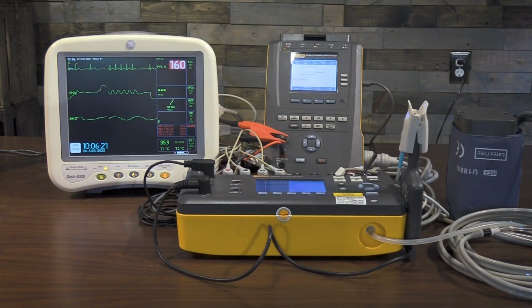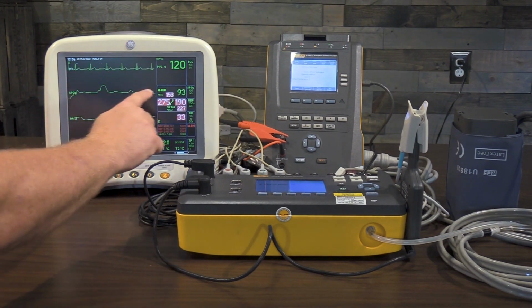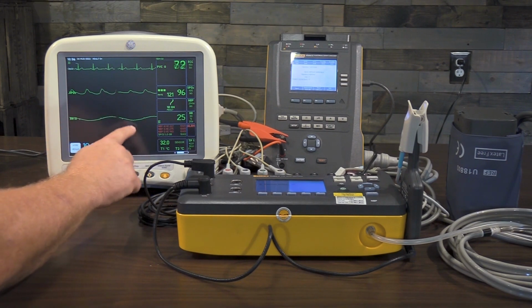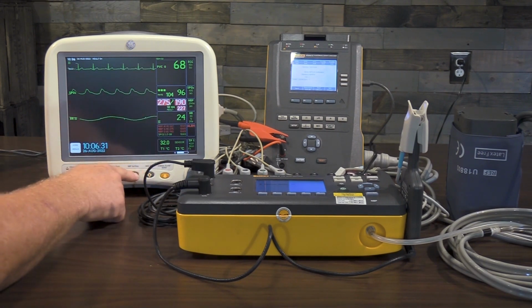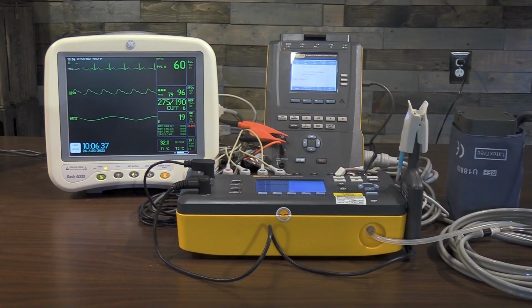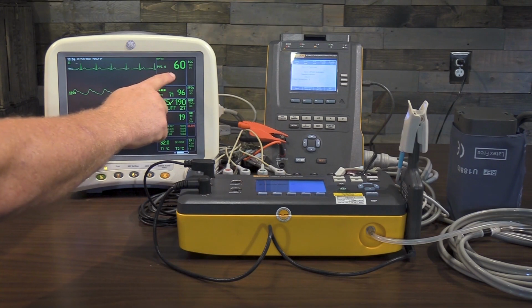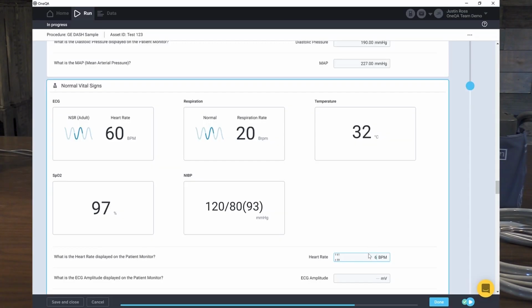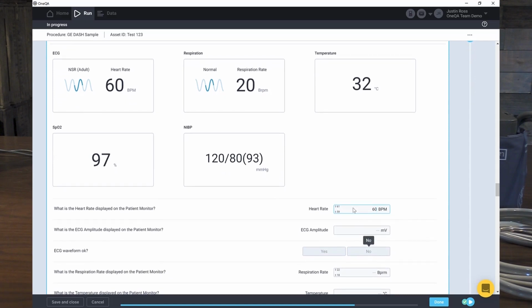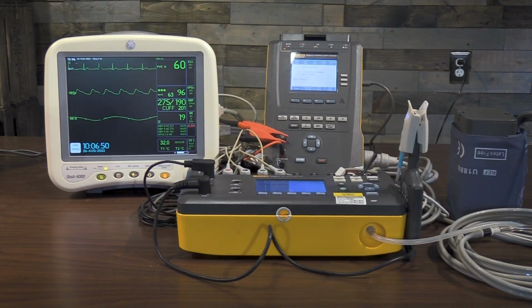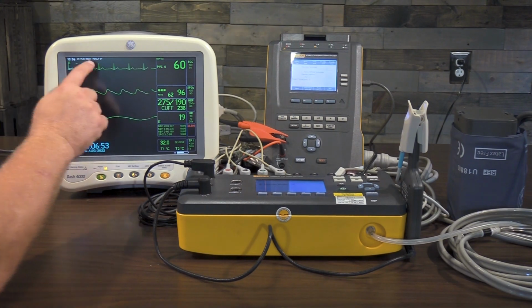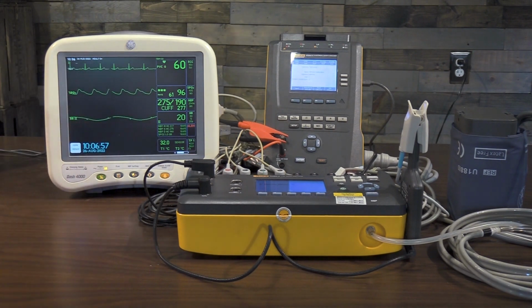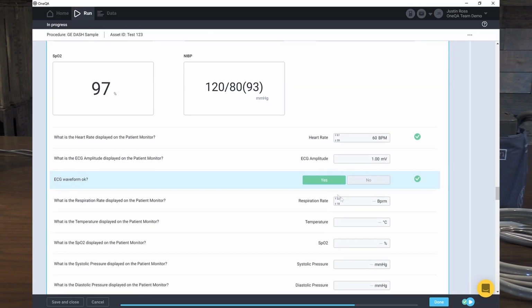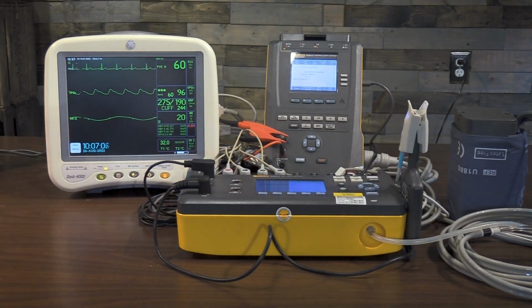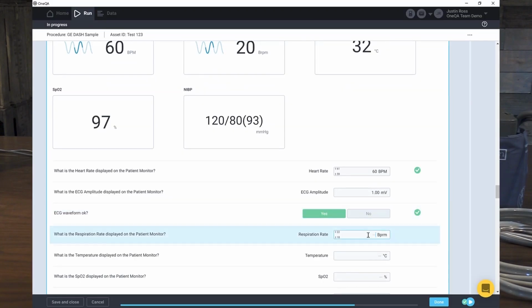I click there, and you'll see instantaneously all of the parameters are dropping back within line. Now non-invasive blood pressure is still out, so let's run our non-invasive blood pressure again. All right, so all of our alarms are shut off. Our heart rate we have set at 60 and we're displaying 60, which is good because we only had a tolerance of 1. Our ECG amplitude is still ranging at 1 millivolt. The ECG waveform, there's a little bit of interference on there. I think we have a bad lead, so we can replace that for today. We'll call it good. Our respirations, that has a tolerance of 2, so we're reading at 20. It was set at 20, so we'll put that in here and see if we pass.